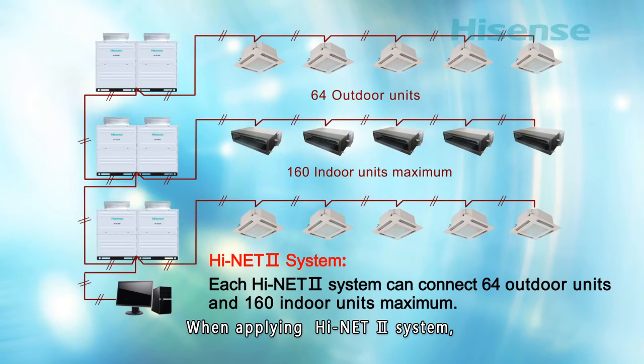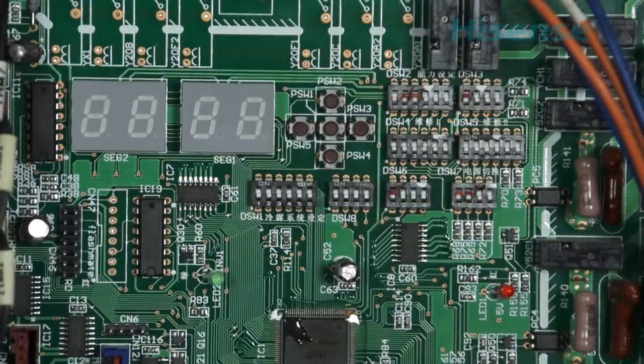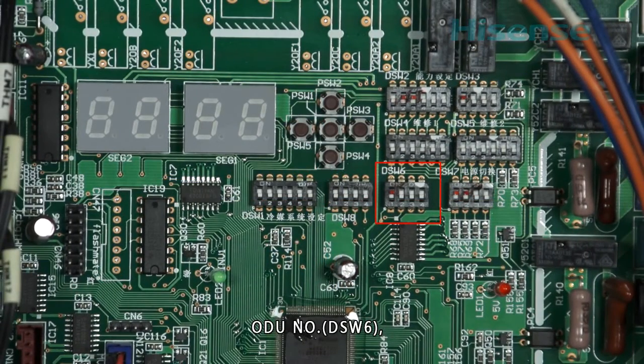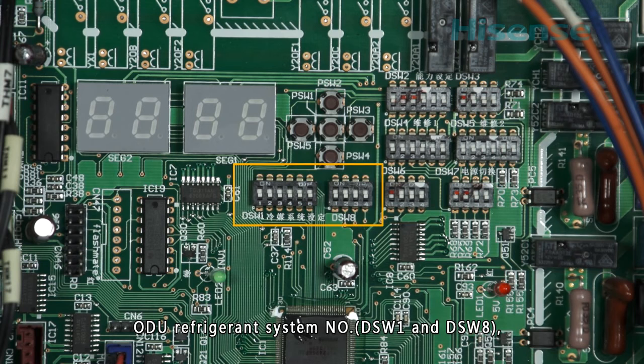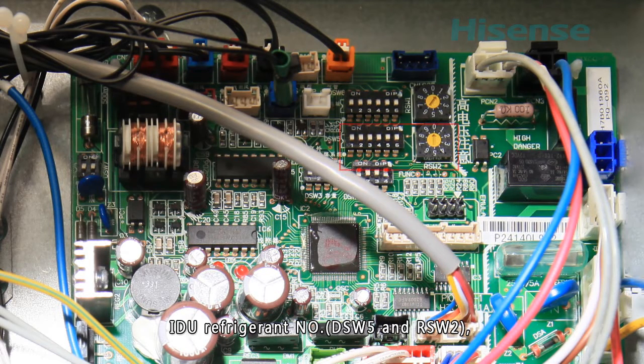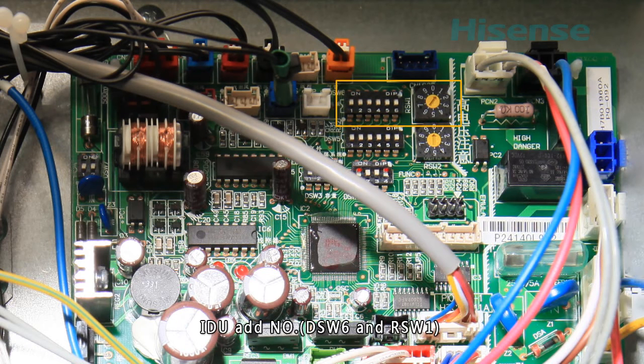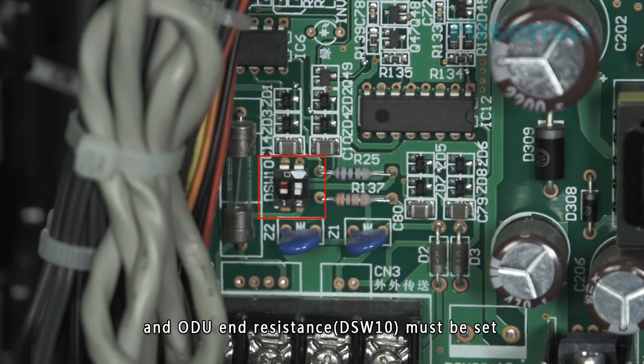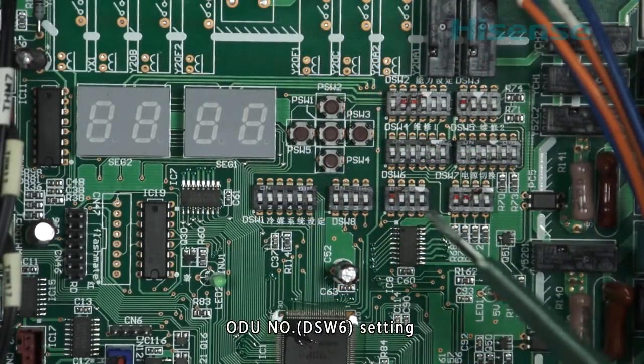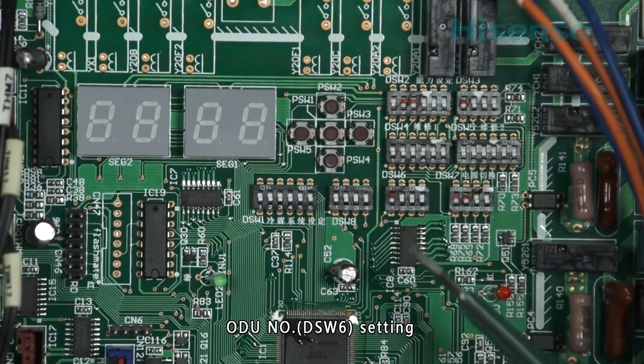When applying Hi-NET II system, outdoor unit number DSW6, outdoor unit refrigerant system number DSW1 and DSW8, indoor unit refrigerant number DSW5 and RSW2, indoor unit address number DSW6 and RSW1, and outdoor unit end resistance DSW10 must be set. Outdoor unit number DSW6 setting.